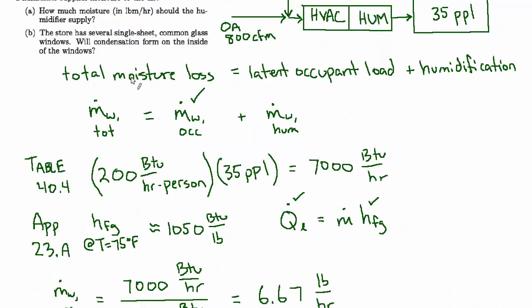And now circling all the way back to our original equation: total moisture loss equals latent occupant load plus humidification. We now know the occupant load, we know the total moisture loss. Let's rearrange this and subtract total minus occupant to find the humidification.